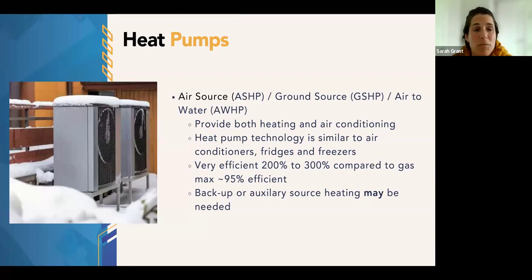And in the case when it's a hybrid system, if you're not aiming to electrify fully, you would have a heat pump, and then at some point the thermostat will notice that the heat pump doesn't have the capacity and it'll switch over to a gas furnace. If you want to electrify fully, which I really encourage, then in that case, the heat pump is still going to run all winter long, because remember, it works up to minus 30. So it'll continue to provide heat. It's just that at some point, the heat loss in your home may be greater than what that heat pump can provide. So the thermostat will take note of that, and it'll ask for an auxiliary source of heating, which is electric, to come on and give a boost.